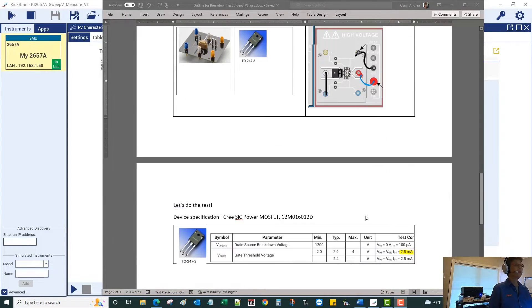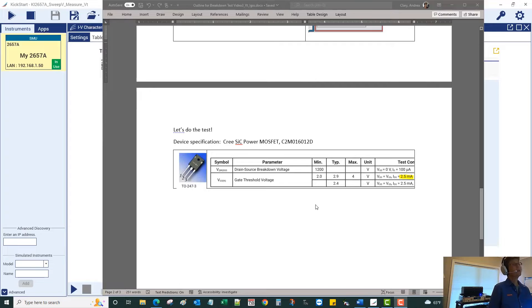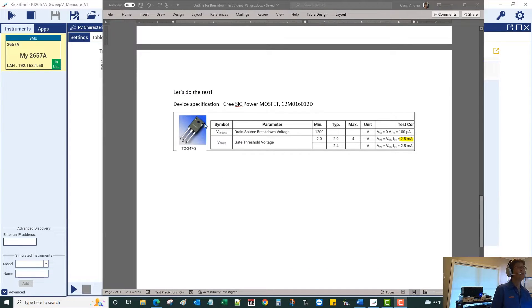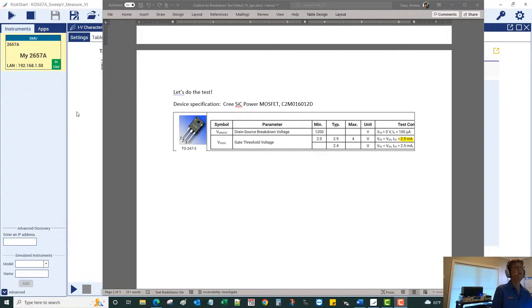Let's switch over, do the test. As a reminder, we're going to sweep — we're looking for 2.5 milliamps, and the threshold voltage should be more than two and less than four, but typically 2.9.